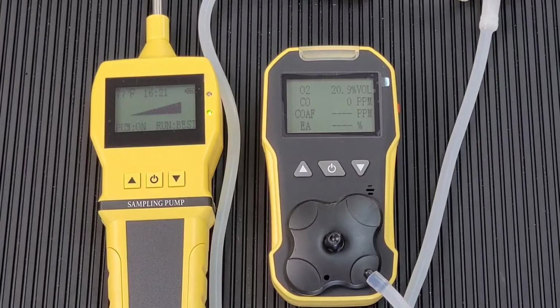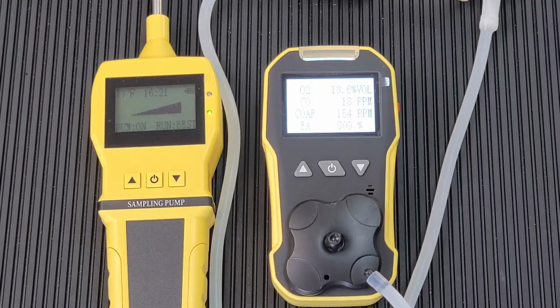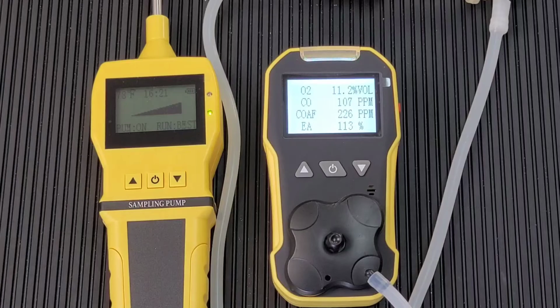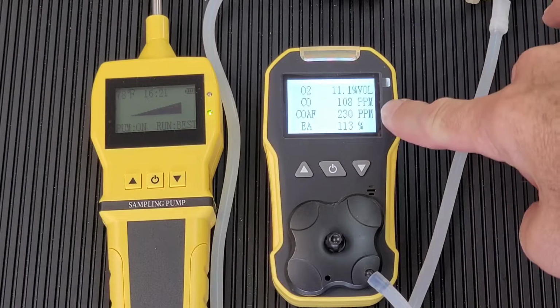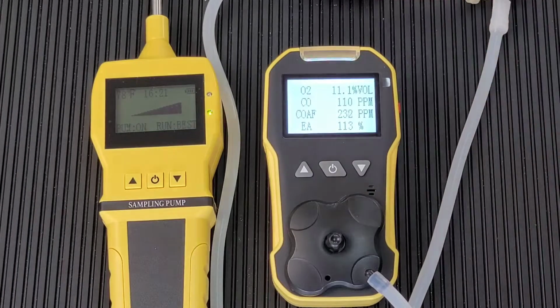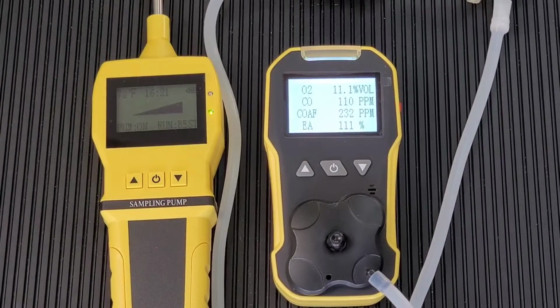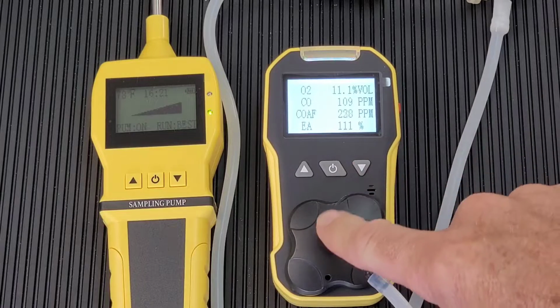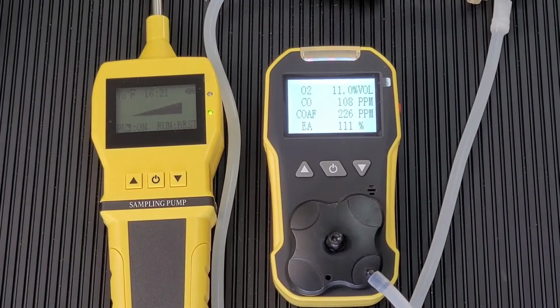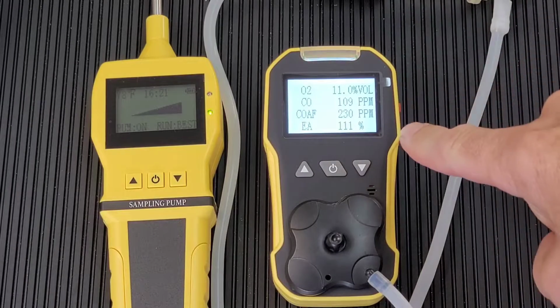I've just turned on the gas and we're going to see the numbers starting to climb and the oxygen going down. Okay, folks. I'm going to pause it and come back once it's stabilized, because it could take about a minute or so. Okay, here we are with the basic setup. We're seeing the CO pretty much on the mark here. The bottle, again, I emphasize, is 106 ppm of carbon monoxide. We're actually overshooting a little bit with our setup. The oxygen is 10%, and we're overshooting on the oxygen, about 11%.